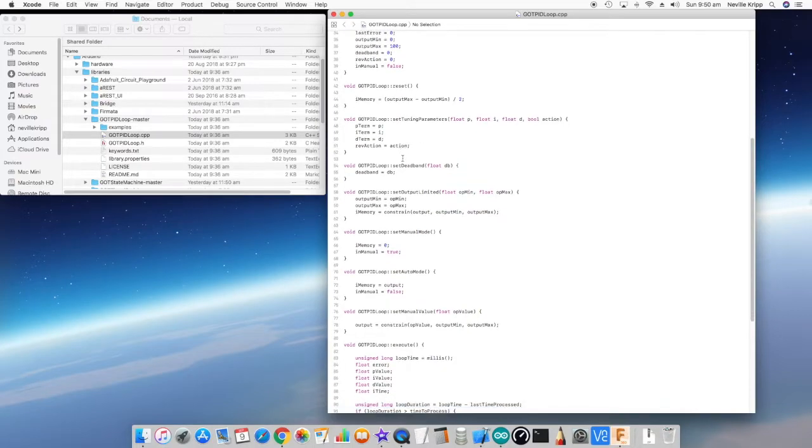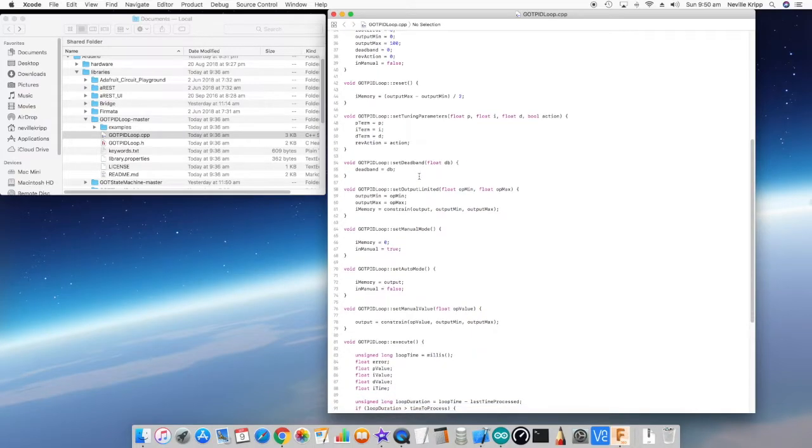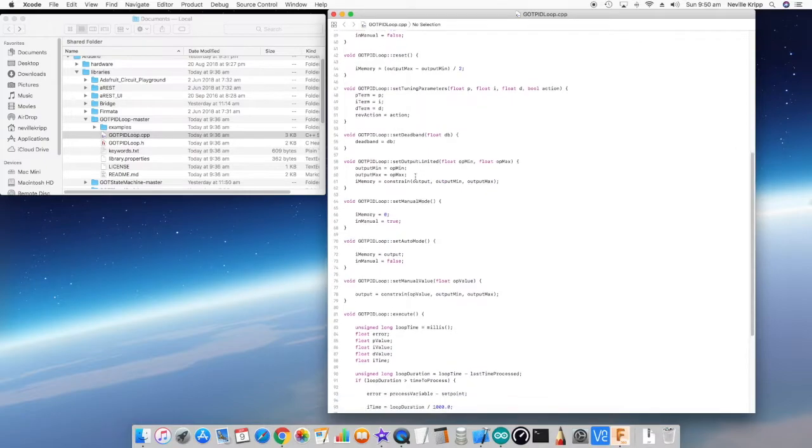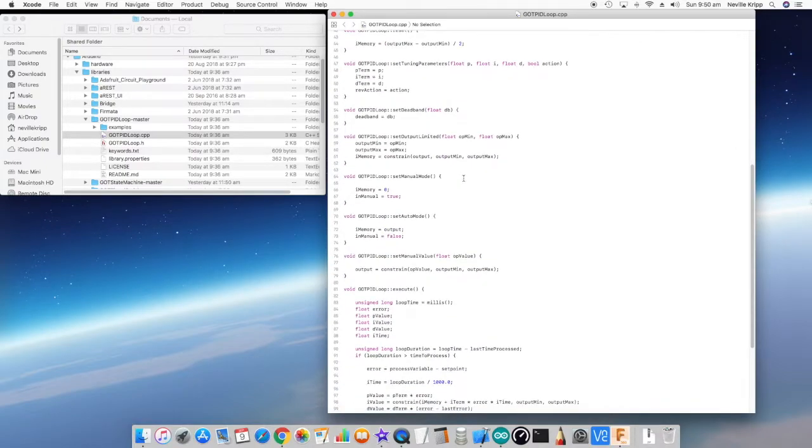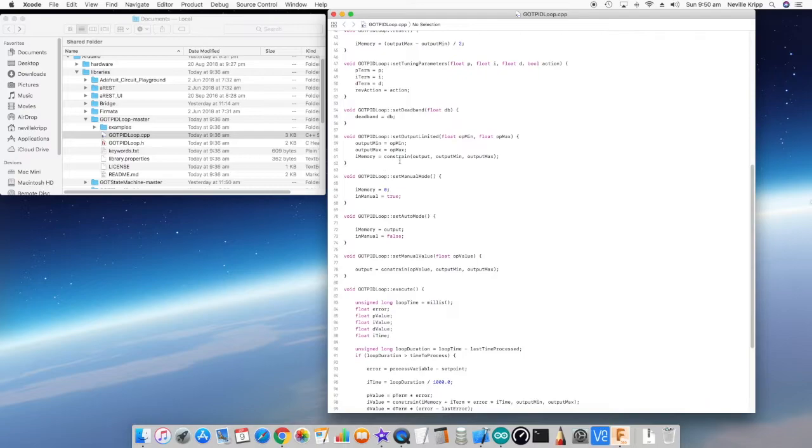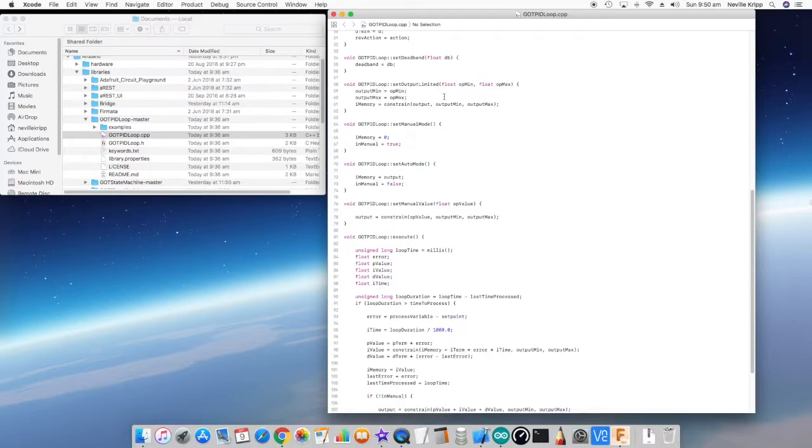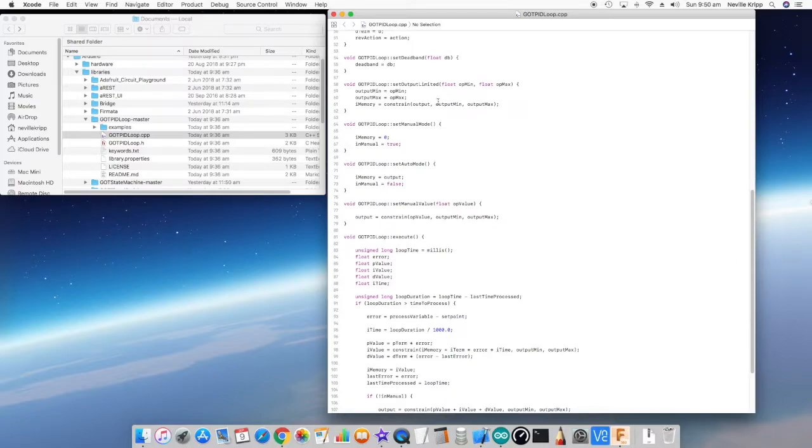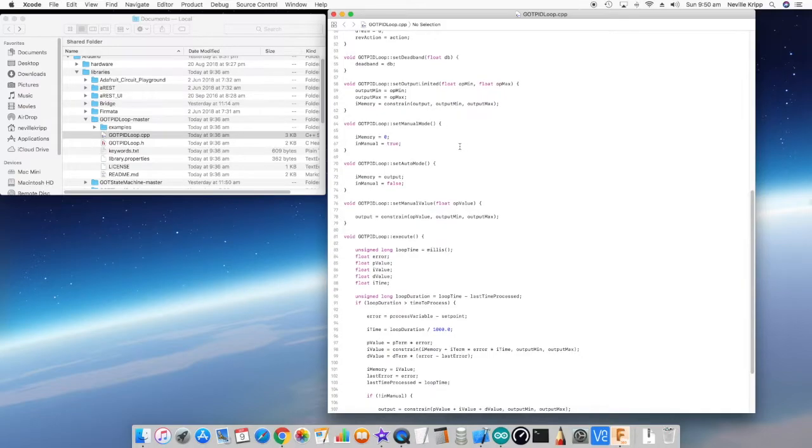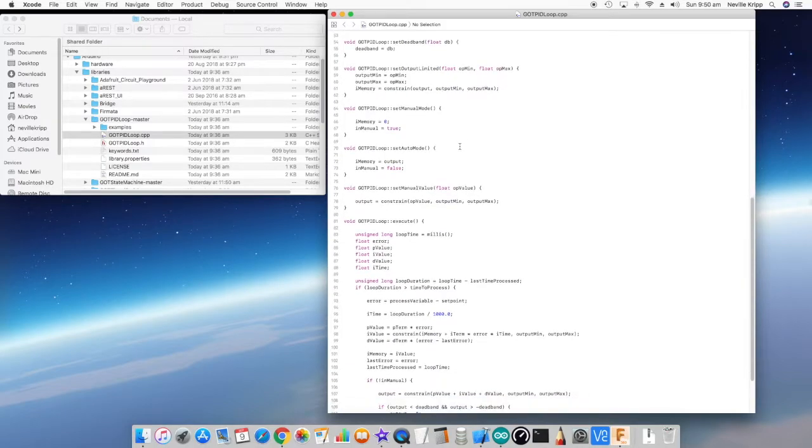The next thing is we get to set tuning parameters where the parameters are just passed through and saved to internal variables. Same with dead band, and the same with the output limit. The only thing with the output limit is when it is set, if there's been a change or something like that, the i memory gets constrained within that range. After doing that, you should always call the reset, but if for some reason you don't, the output will be constrained within those min and max values anyway.